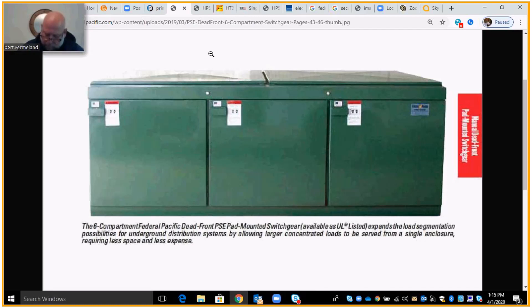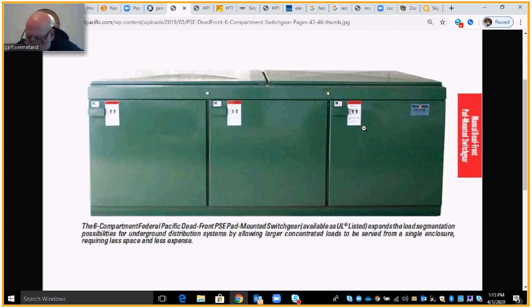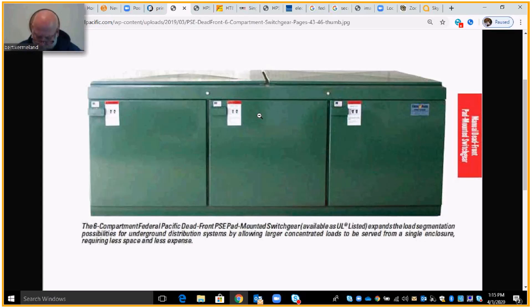In the underground distribution standards manual, a six-four-two switchgear designates six total compartments, four feeder compartments, and two tap compartments. They can be made in any configuration you need — you can have a six-two-four (six total, two feeder, four tap). For a four-compartment switchgear, you can have a four-two-two (four total, two feeder, two tap). Its purpose is to switch feeders around if you need to change the feed of different feeder lines, and have taps going to different equipment. There is no transformation — it's just a junction point for feeders and taps.